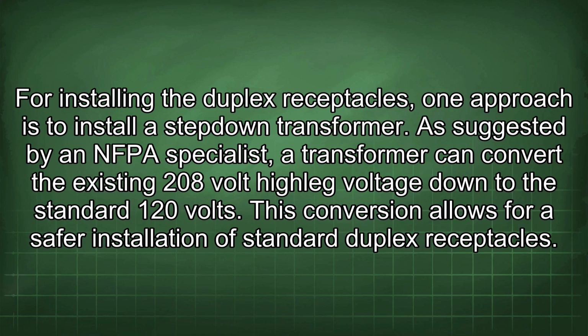For installing the duplex receptacles, one approach is to install a step-down transformer. As suggested by an NFPA specialist, a transformer can convert the existing 208-volt Highleg voltage down to the standard 120 volts. This conversion allows for a safer installation of standard duplex receptacles.